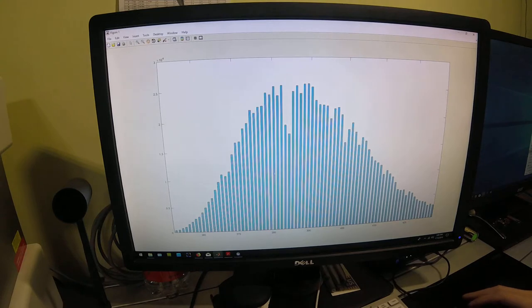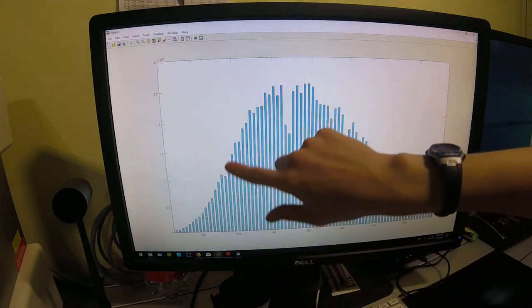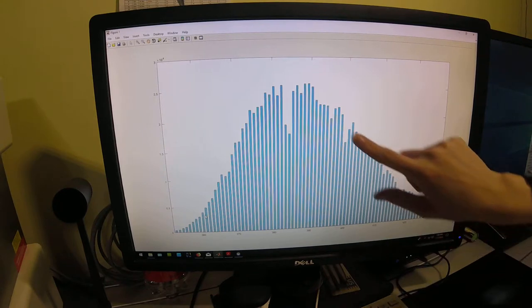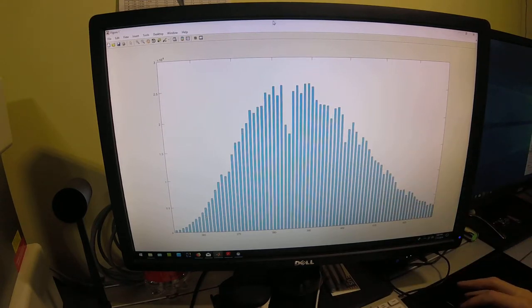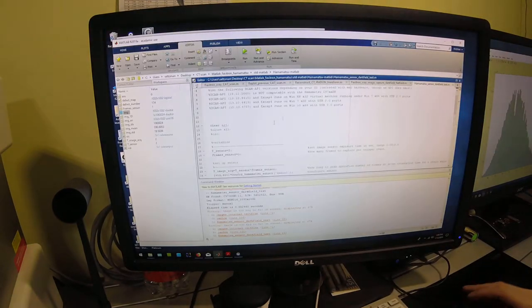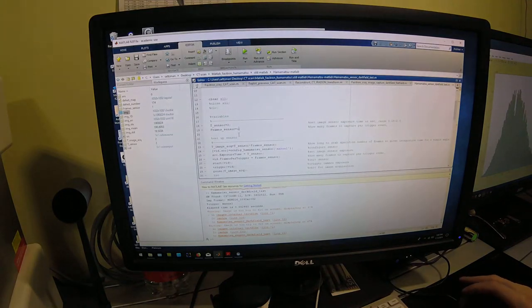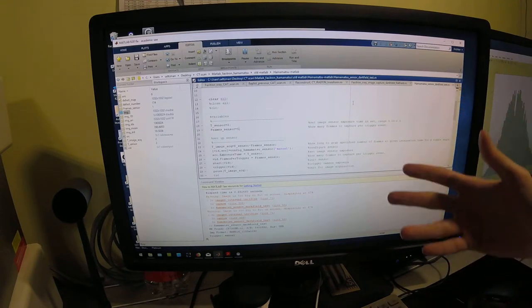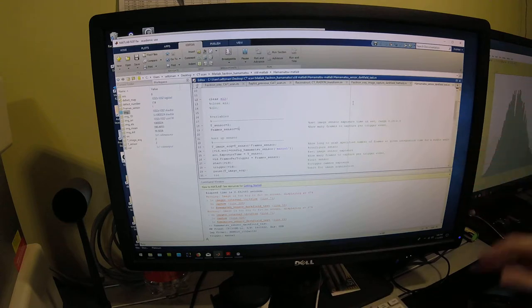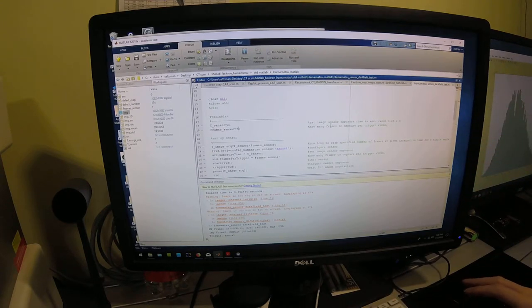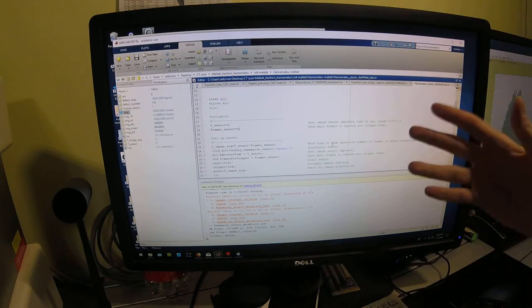If we remember the histogram here, we can see that there is some variation on the profile. It's not entirely smooth; there are some dips. To improve those statistics, we can take multiple frames. So let's take a 5-frame per trigger capture. Now it's going to take 10 seconds of total integration time divided into 2-second frames, and when that's done, it's going to return the frames to the computer.